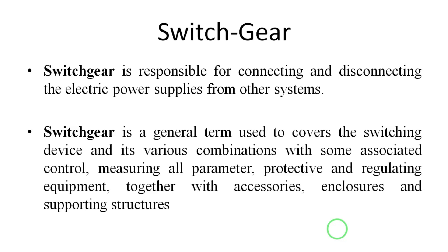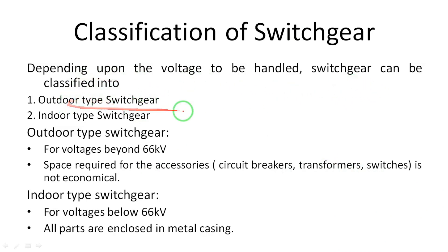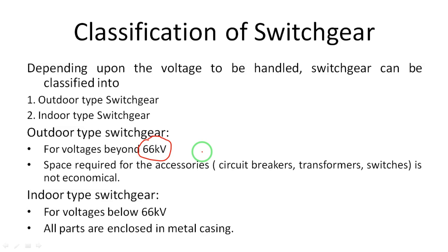Now, the main classification of switchgear depends upon the voltage to be handled. There are two types: outdoor type switchgear and indoor type switchgear. Outdoor type switchgear is used for voltages beyond 66 kV. In substations we have voltage levels of 33 kV, 11 kV, 66 kV, 132 kV, and 220 kV. For voltages beyond 66 kV we use outdoor type switchgear, and for voltages below 66 kV we use indoor type switchgear.